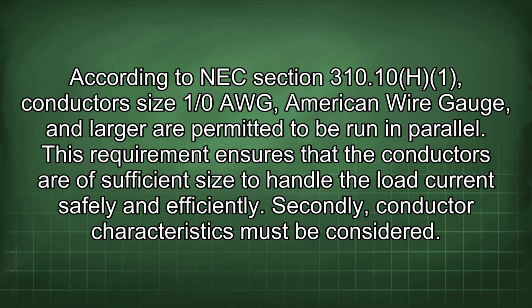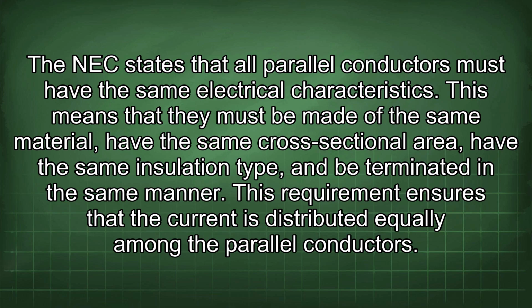Secondly, conductor characteristics must be considered. The NEC states that all parallel conductors must have the same electrical characteristics. This means that they must be made of the same material, have the same cross-sectional area, have the same insulation type, and be terminated in the same manner. This requirement ensures that the current is distributed equally among the parallel conductors.